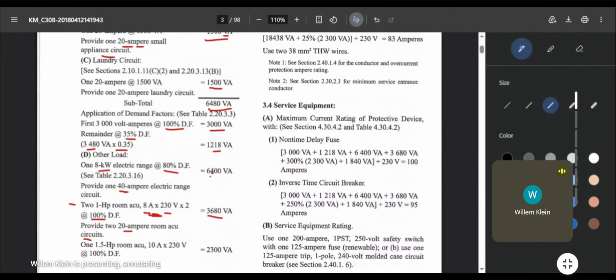Again, our motor loads, like I mentioned before, have high starting current. So imagine if you're only using one 20 ampere circuit breaker, and then you have two aircons, and you turn them on simultaneously. Knowing that they will consume a large amount of starting current to operate, what will happen to your breaker? It will trip because it will think that there's an overcurrent. So that's why it's important to only use one circuit breaker for each aircon.